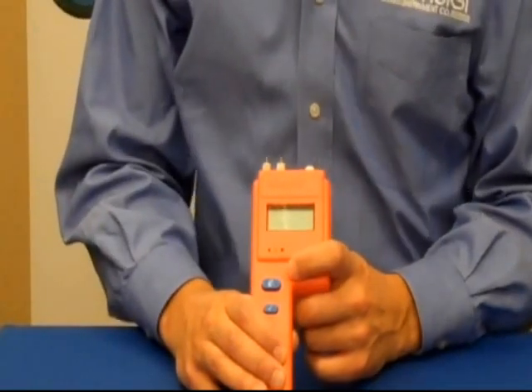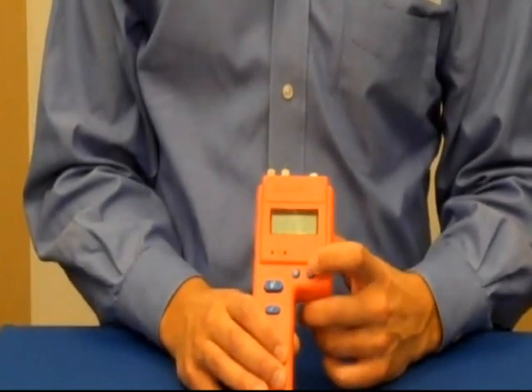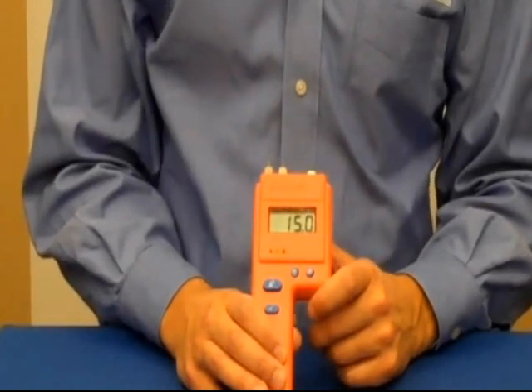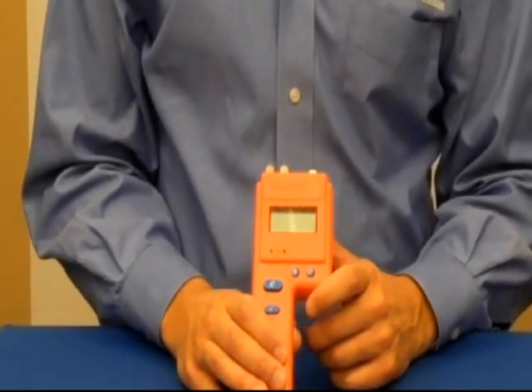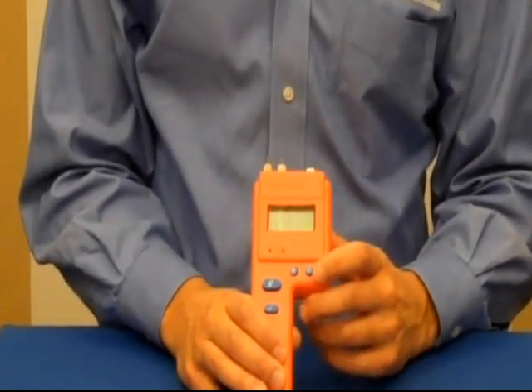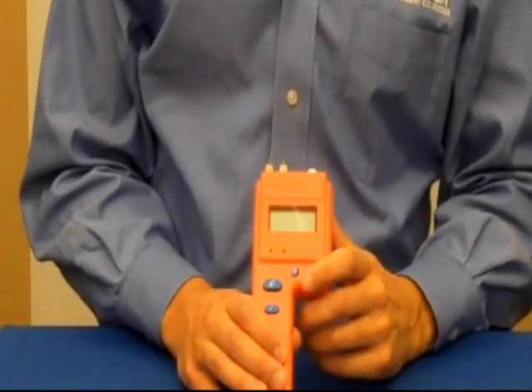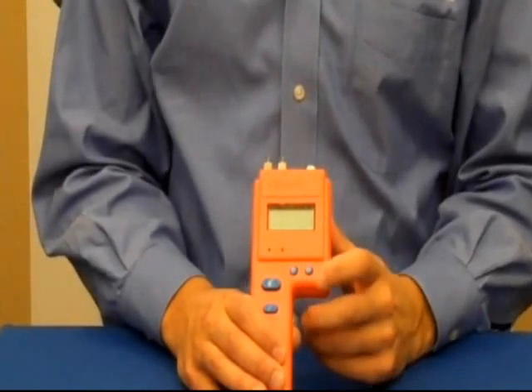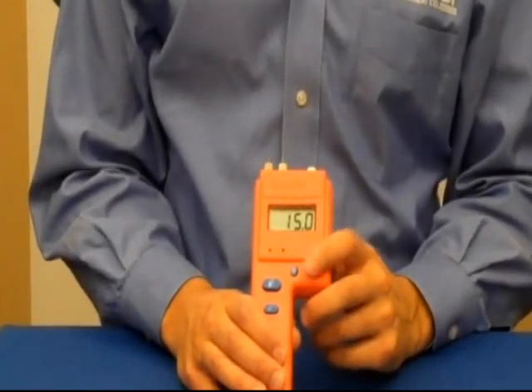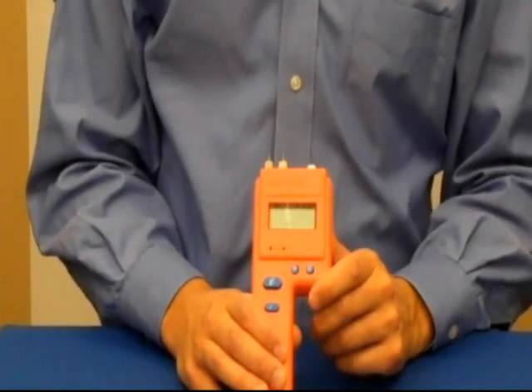Once you've set your scale to the material that you're testing, you can adjust the alarm by pressing the pound key. The alarm is user adjustable and it's a really great feature because it allows you to go into a job, identify an unaffected area or a dry standard, and then set the alarm to that value.